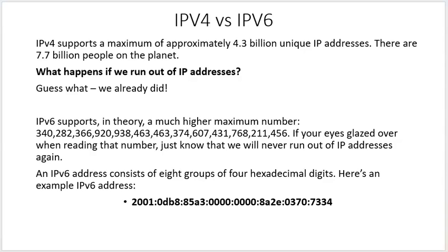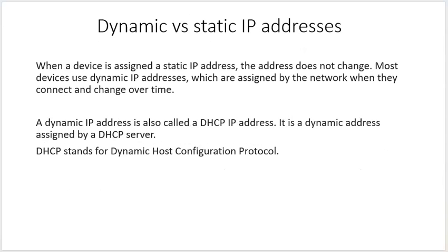Inside a DICOM network, all of those IP addresses will be unique to that network. Okay, so the 4.3 billion unique IP addresses only relates to the internet. Right? So the internet is a giant global network. So for everything to be unique on the internet, well, obviously 4.3 billion wasn't enough. But inside your DICOM network, you're only going to have 100, 200 devices connected. So inside a DICOM network, everything is IP4. So you will never need IP6 unless you're dealing with a connection outside of your building. That's what I'm trying to say.